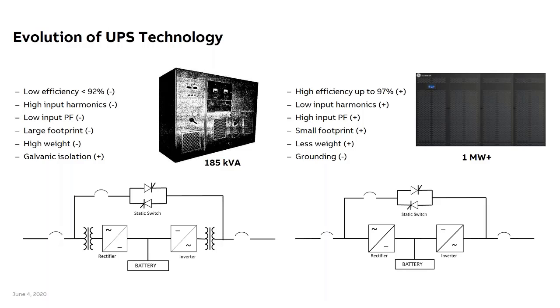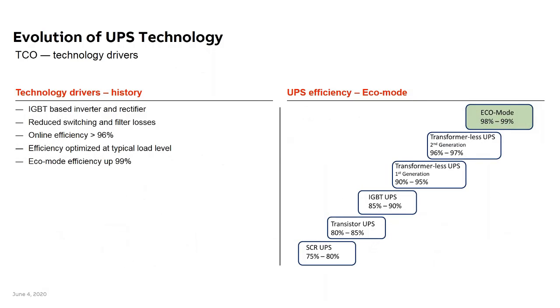The filters were needed, the transformers were needed. Since then, with the modern IGBTs that are easily available to handle way more than normal line voltage, and very fast switching, we don't need the transformers. We don't need the filters, at least with very limited filters. The benefit, of course, is we got rid of all that heavy magnetics, and with that, a lot of the heat loss in UPSs. So compared to then, very high efficiency, very compact, very light compared to yesteryear's UPS design. But they work pretty much the same way.